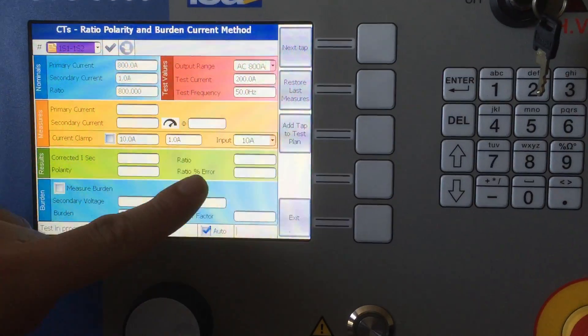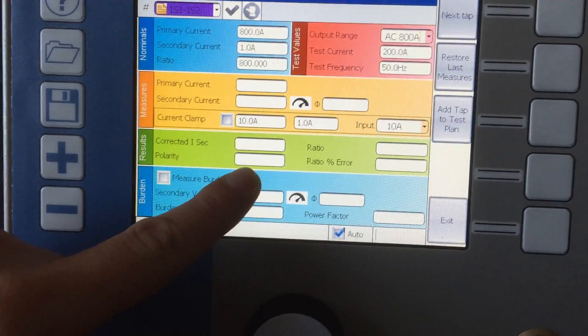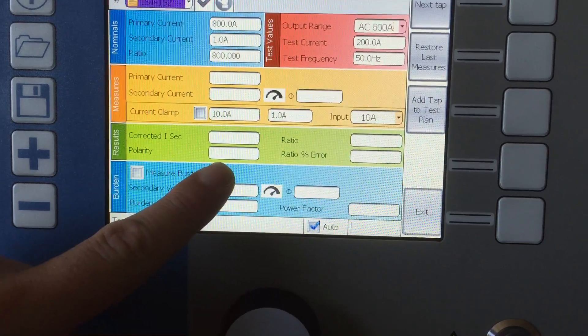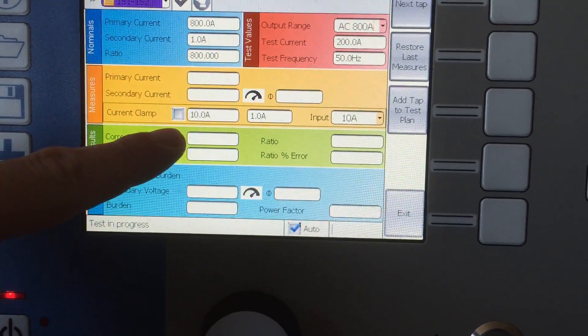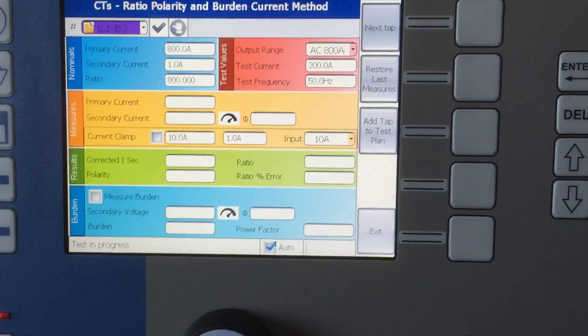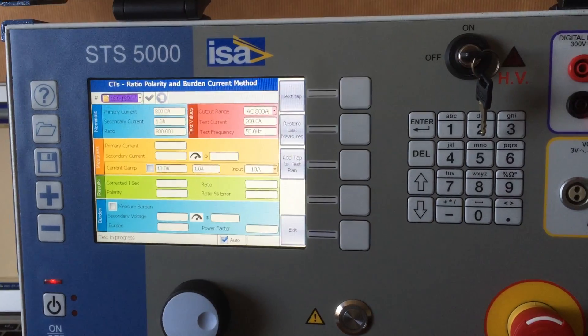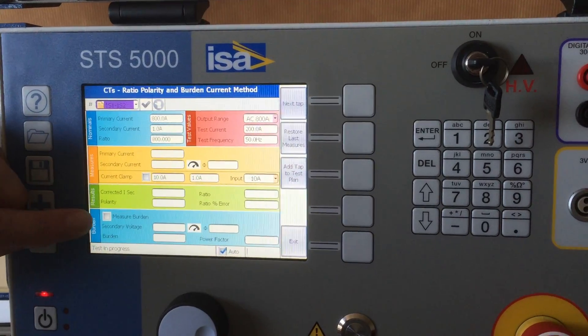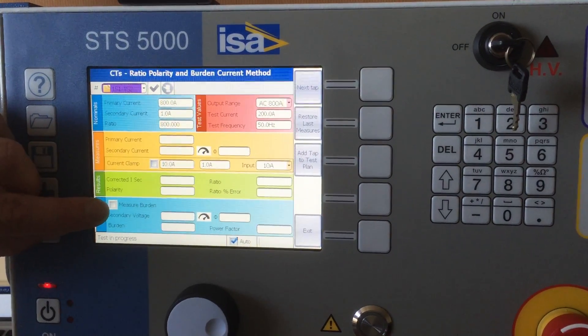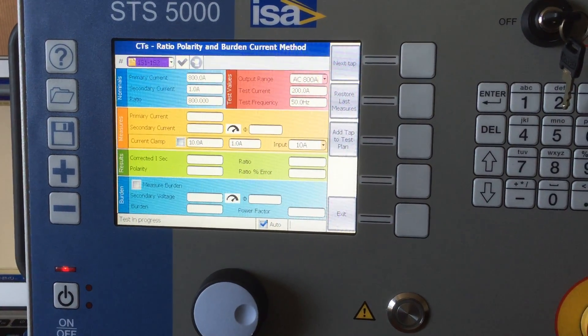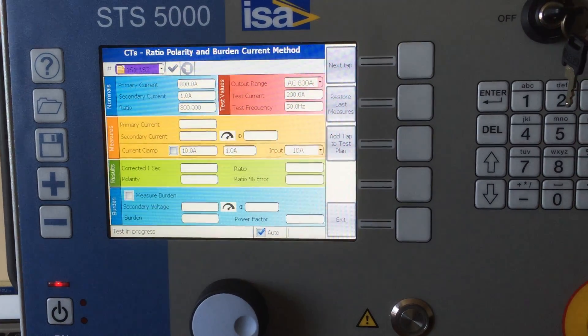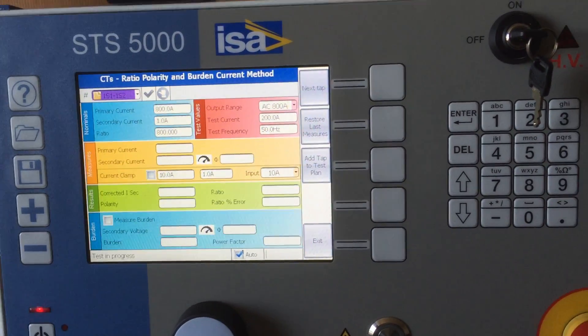What is the actual ratio? What is the ratio error? And you get the information about the polarity and the corrected secondary current. This completely tests your ratio. And you can also, if you decide to put a tick here, measure the burden on your CT — because you have to see how much burden you're supplying.